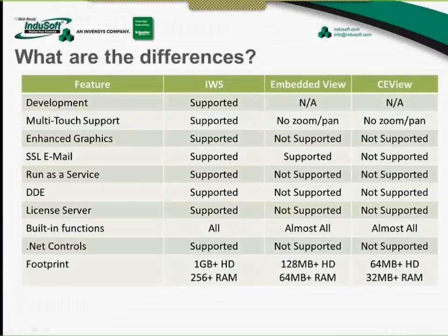Okay, so continuing here, runtime as a service, or run as a service. That is allowed in InduSoft Web Studio, but it's not supported by embedded view and CE view. And usually, if you have an embedded panel, you want the embedded panel to start and run your application, automatically log on. So it's different from a server, where you usually want to run as a service. So that capability is not supported on embedded view and CE view.